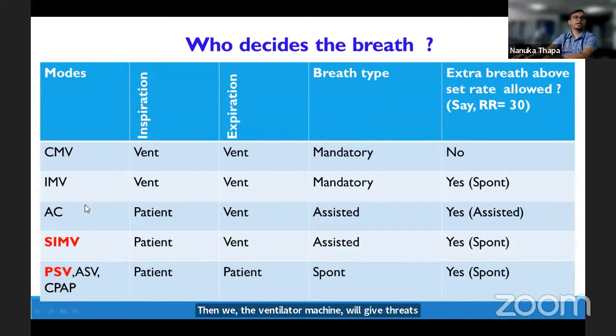In CMV and IMV, inspiration and expiration are given by the ventilator. Both breaths are mandatory breaths. For CMV mode, we set the ventilator breaths, for example, the respiratory rate we set at 30. The ventilator will give 30 breaths, and extra breaths above this will not be allowed by the ventilator. In IMV mode, even after setting the respiratory rate of 30 breaths given by the ventilator, spontaneous breaths are allowed. In assist control, the difference is that inspiration is started by the patient, expiration is initiated by the ventilator, and it allows assisted breath.